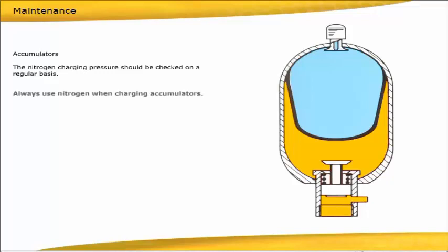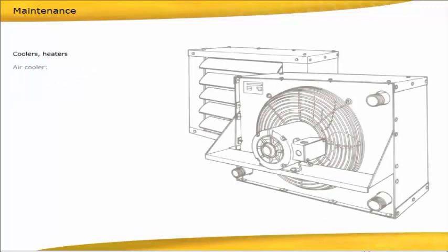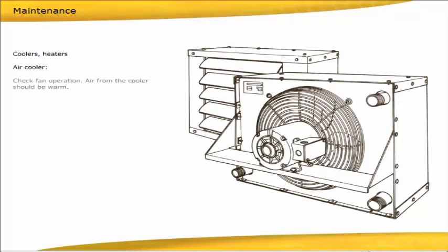Coolers and heaters. Air cooler: Check fan operation. Air from the cooler should be warm. Water cooler: If the cooler is not efficient, high oil temperature, the cooler may be clogged. Heaters: Check set point and operation.